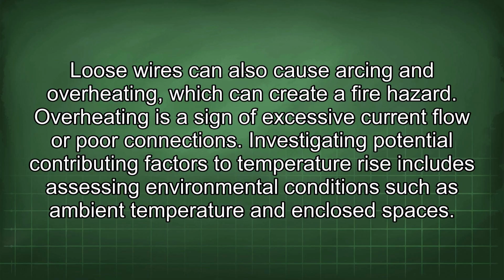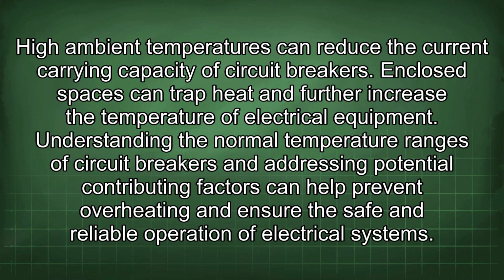Investigating potential contributing factors to temperature rise includes assessing environmental conditions such as ambient temperature and enclosed spaces. High ambient temperatures can reduce the current carrying capacity of circuit breakers. Enclosed spaces can trap heat and further increase the temperature of electrical equipment. Understanding the normal temperature ranges of circuit breakers and addressing potential contributing factors can help prevent overheating and ensure the safe and reliable operation of electrical systems.